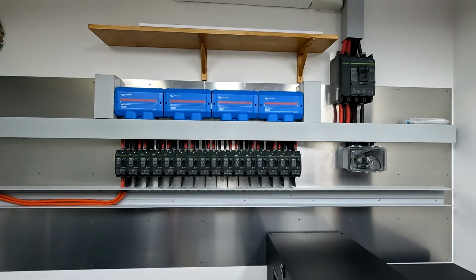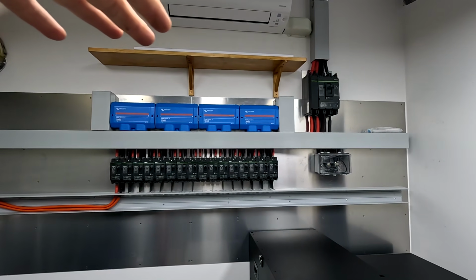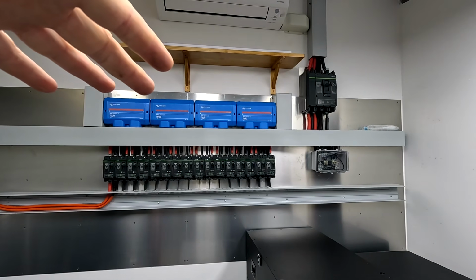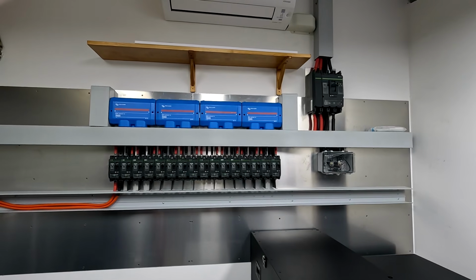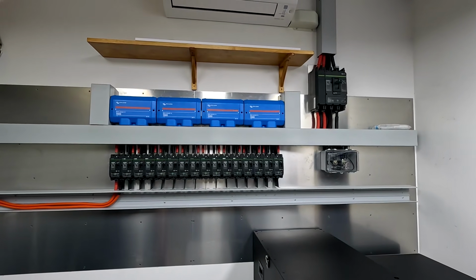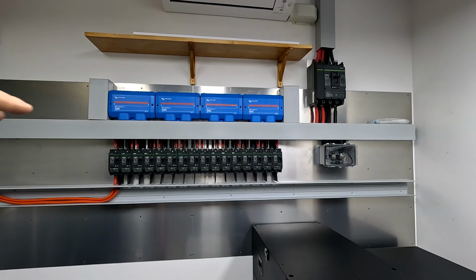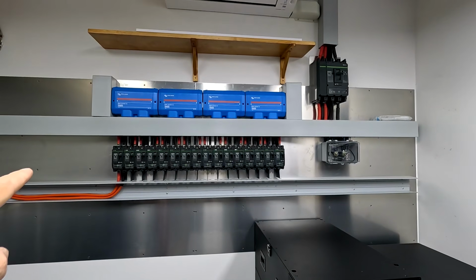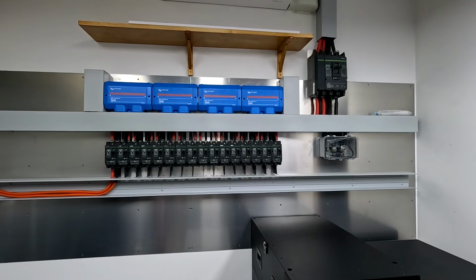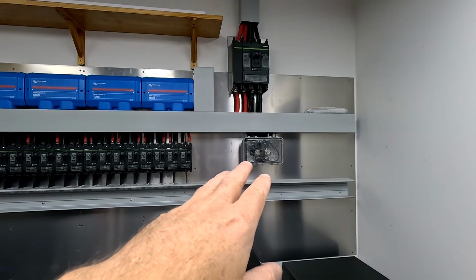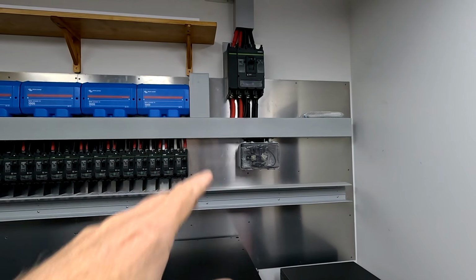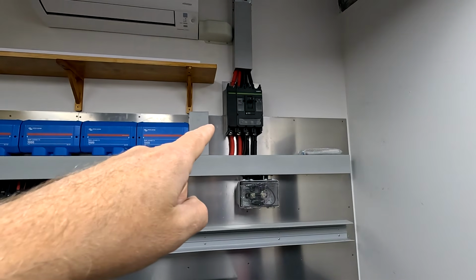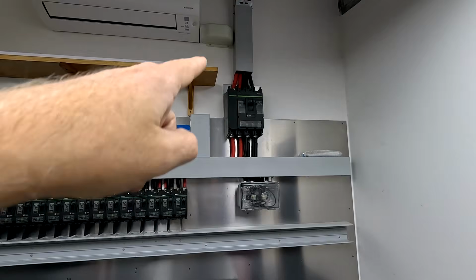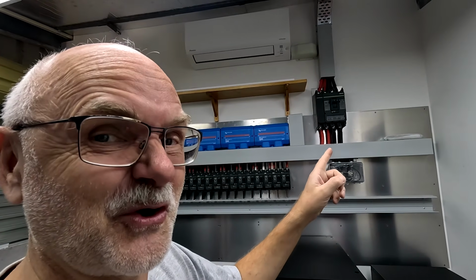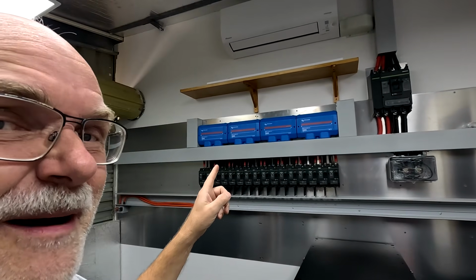We have finalized the top part of the battery wall, the power battery extension wall. You can see the Victron bus bars up there, the nice cable duct now, everything is closed, and the 16 MCCBs down here to connect to the batteries. The smart shunt cabling is all fixed up now. I still need to design and print some covers, some shrouds for this MCCB, and it is almost time to turn this beast on and power up this bus bar.